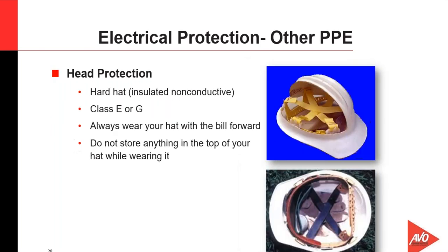Head protection, we're looking at electrically rated hard hats for testing and maintenance. Class E or G would work. Always wear the hat appropriately with the bill forward, the suspension adjusted, and don't store anything up in top like the gloves on the bottom. You can see they're using their hat as a kind of a storage bin.